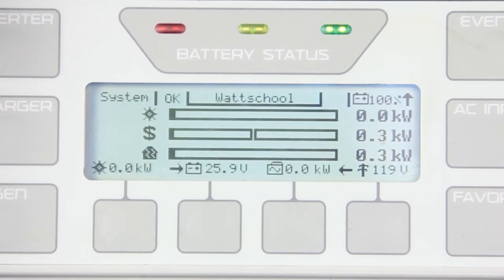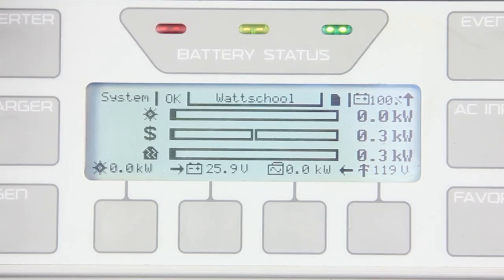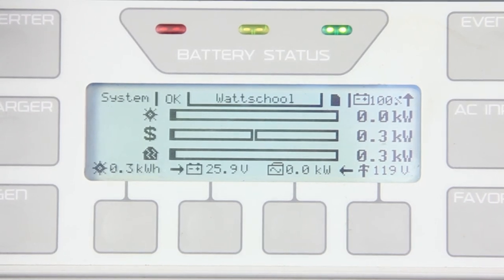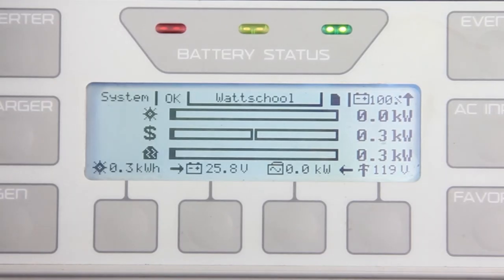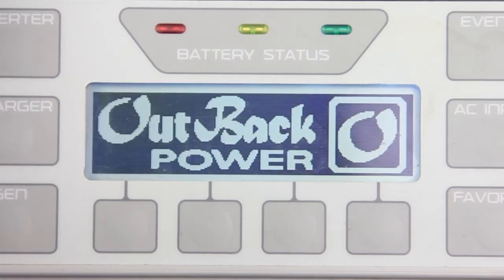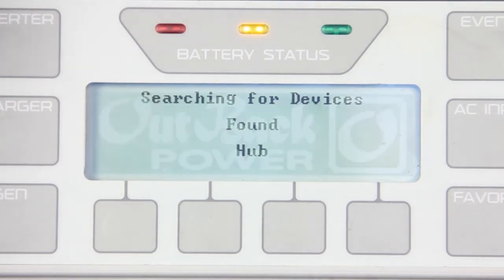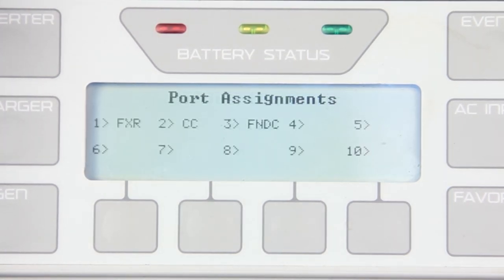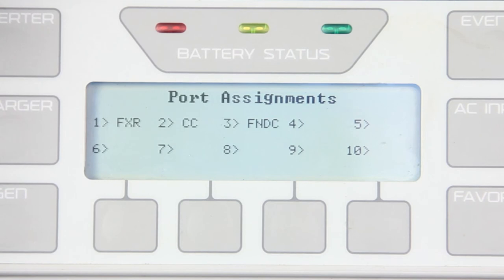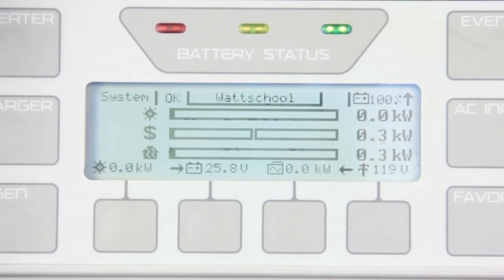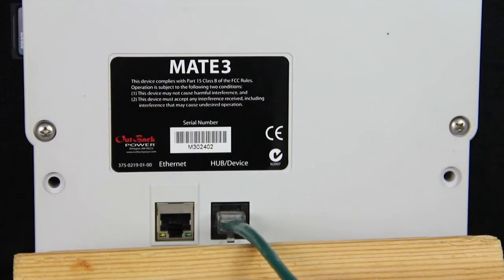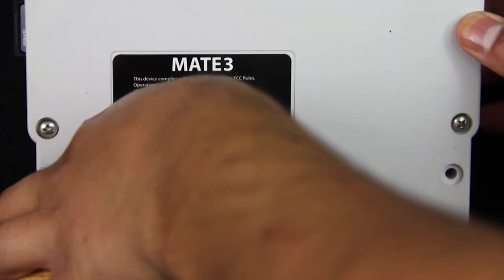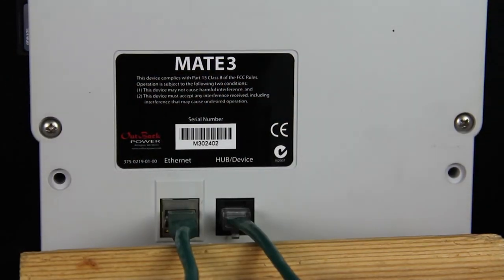Warning, to prevent permanent damage of the device, allow an additional 2 minutes for the update to complete before you press any buttons. Finally, after the 2 minute wait, power cycle the Mate 3. Reconnect the Ethernet cable and allow the Mate 3 to connect to your network.